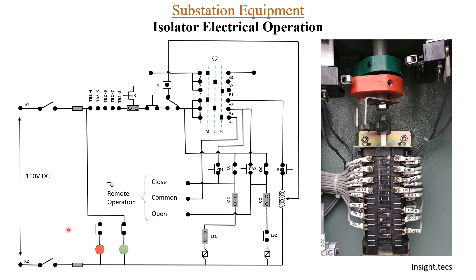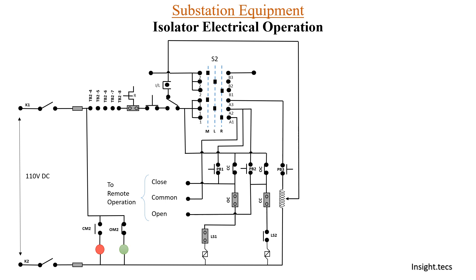Additionally, CM2 and OM2 auxiliary switch contacts are used for the LEDs and are also very important for other purposes — such as taking the status of the isolator for SCADA indication, or for bus bar protection which depends on the position of the isolator (whether open or closed). In those cases, these auxiliary contacts CM2 and OM2 play a major role.